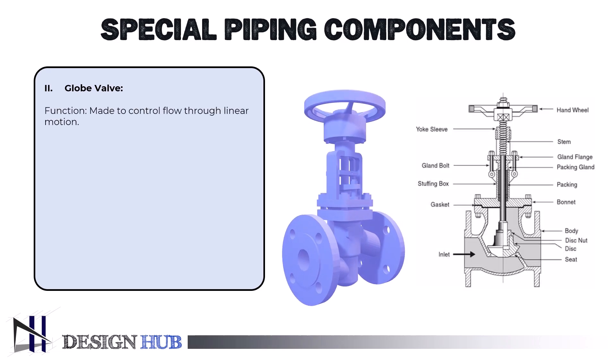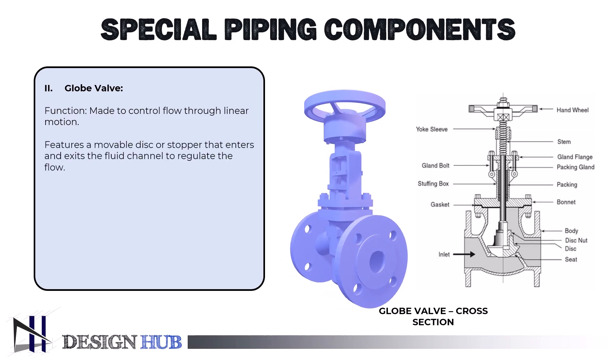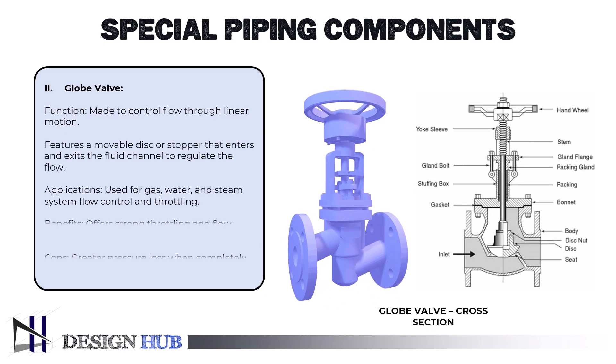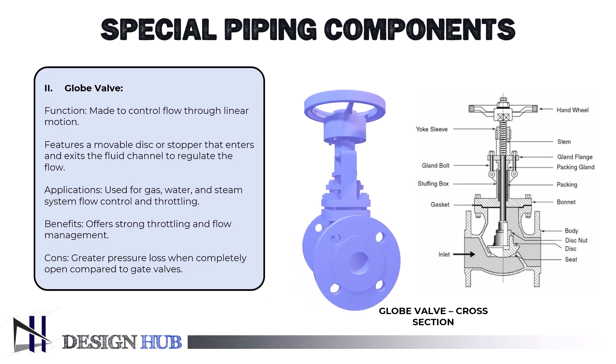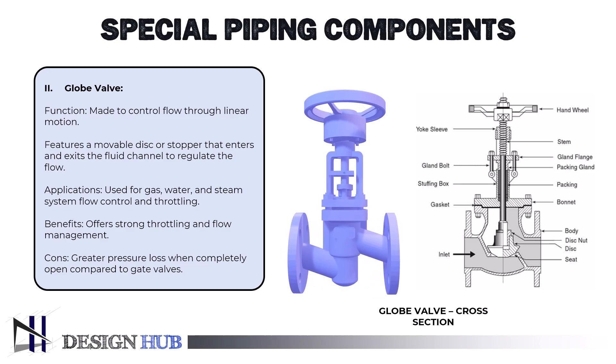Next, let's see what a globe valve is. As opposed to a ball valve, it is a kind of valve used to control flow in a pipeline. It has a stationary ring seat housed in a usually spherical body, together with a movable plug or disc element. Because of their spherical body form and internal baffle dividing their two halves, globe valves get their name. A movable plug can be placed into an opening to create a seat to seal or shut the valve. Globe valves have a plug attached to a stem that is turned by a handwheel in manual valves to control the screw movement.